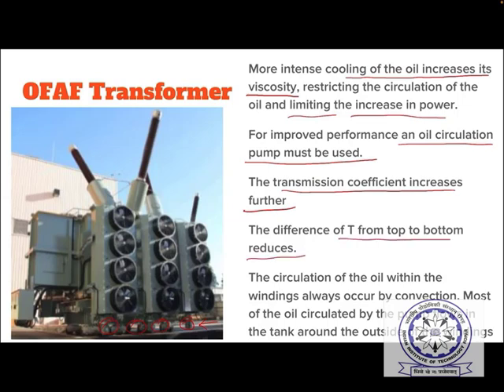Now, this is important. In the previous case, the temperature gradient increased. The oil was not circulated; only the outside cooler was used to decrease the temperature of the oil. So that increases the gradient between windings and oil if the operating power is to be increased by roughly 25%, while maintaining the temperature of the winding the same. So between oil temperature and winding temperature, the gradient is more. But in this case, oil is being circulated now. Earlier, the oil was circulated by natural convection. In this, it is forced by pumps. Therefore, the difference between the top portion and the bottom portion reduces.